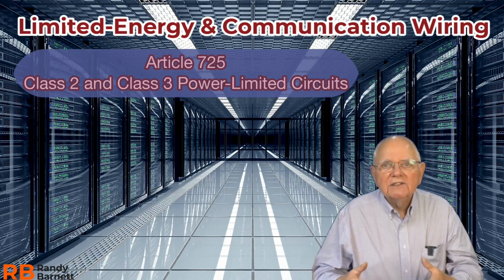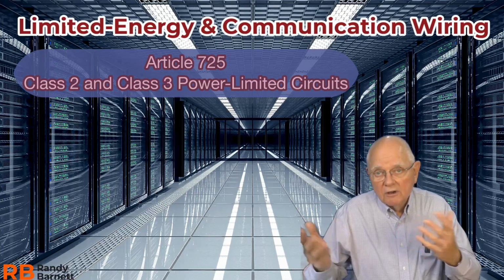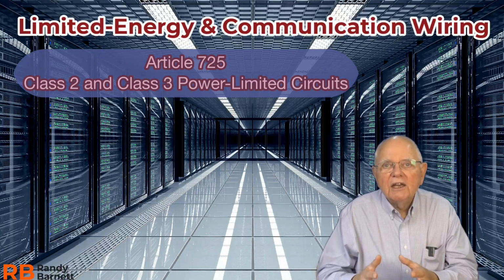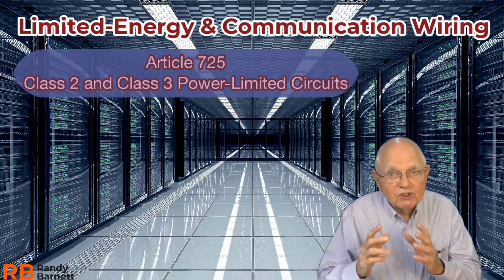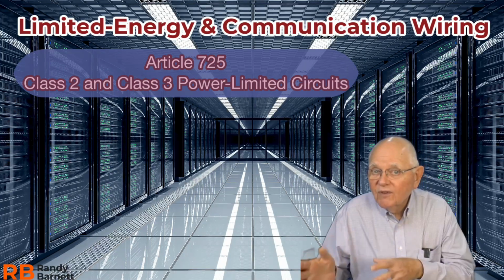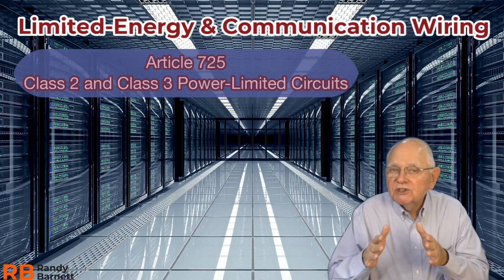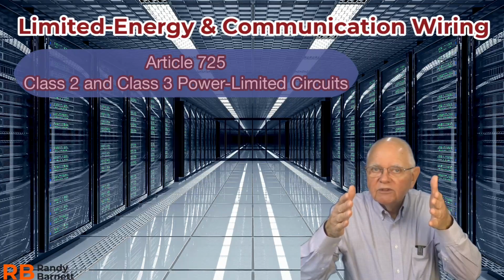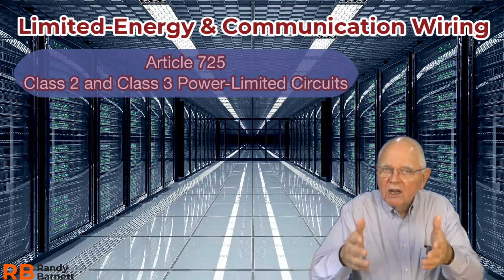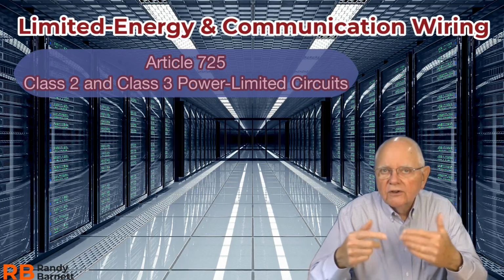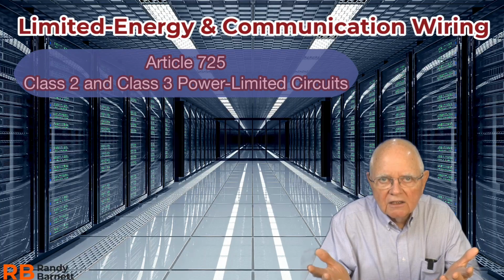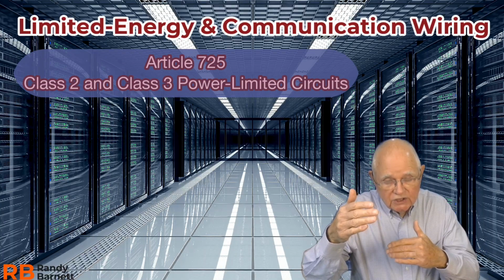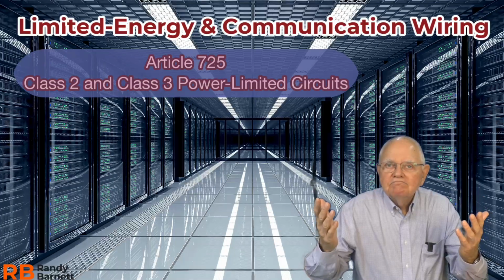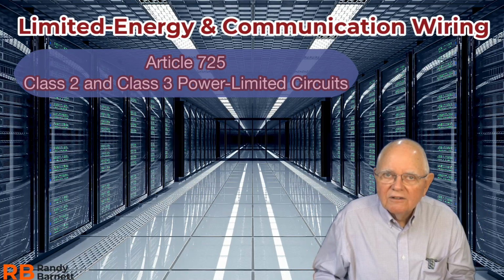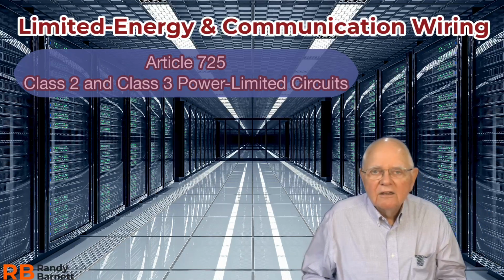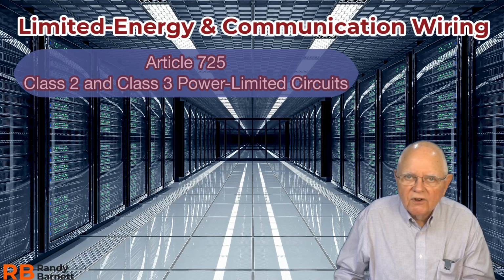It tells us that Class 2 provides ways to mitigate both shock and fire hazards. Class 3 is only good for fire hazards, because a Class 3 circuit actually has higher voltage limitations than a Class 2. A Class 2 is limited to what, 30 volts? So under normal conditions, that's not an electric shock. Class 3, I can have higher limits, and so it's not good for shock protection. So anyway, a little bit of difference between Class 2 and Class 3.